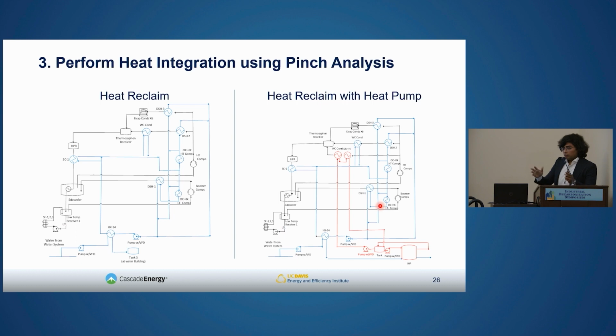Using our pinch analysis, we came up with a system diagram for heat reclaim and heat reclaim with the heat pump option. In our heat reclaim, we're trying to capture that incremental temperature in series. We first go to the subcooler and get all the energy we can out of there, then go to the condenser, then to the oil coolers, and then to the de-superheaters. Through this loop, we've captured all the temperatures in series, capturing as much energy as we could in our hot water system.